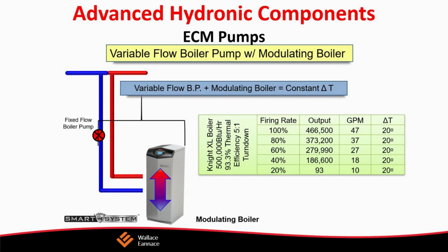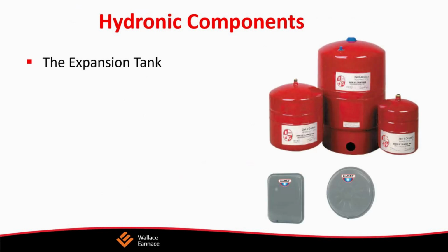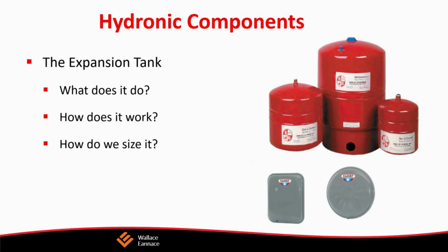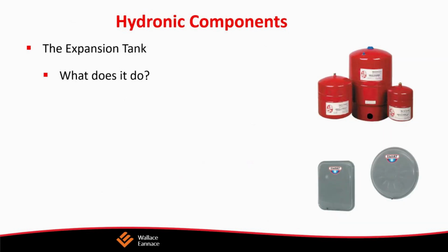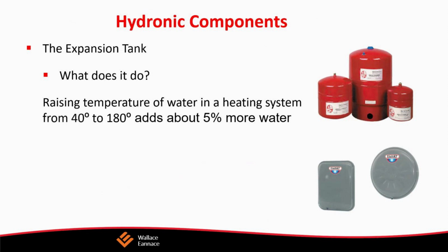Well, what's the advantage to that? Why does that matter? Well, consider that boilers will only condense if the return water temperature is below 140 degrees. So at this point, if we have, say, an output temperature of 150 degrees, we go backwards, and we're running at 20%, we only have a 4 degree delta T, we're going to be returning water at 146 degrees. That boiler is not going to condense. That efficiency is not really going to be 93.3%. It's going to be something less. It'll be probably in the 86, 87% range.